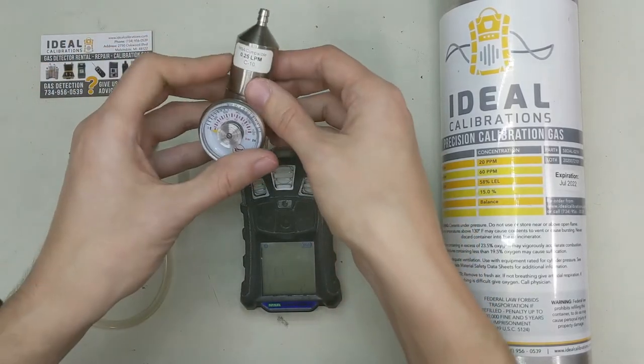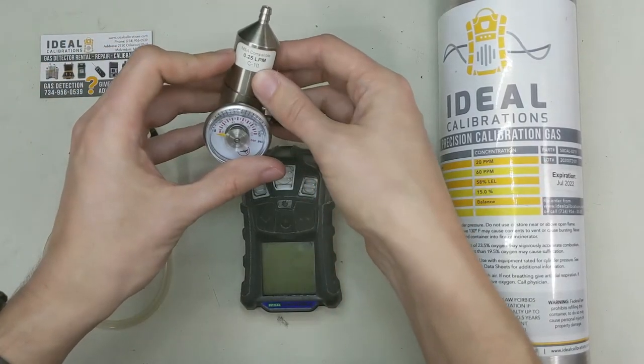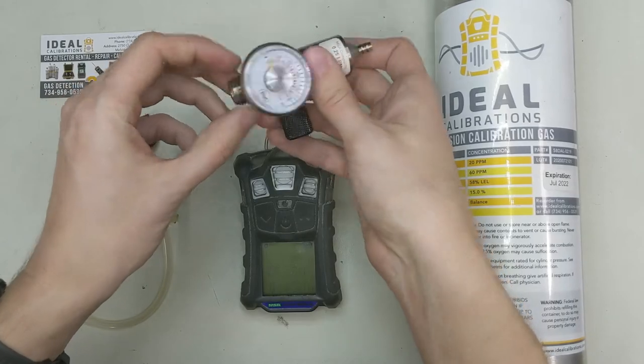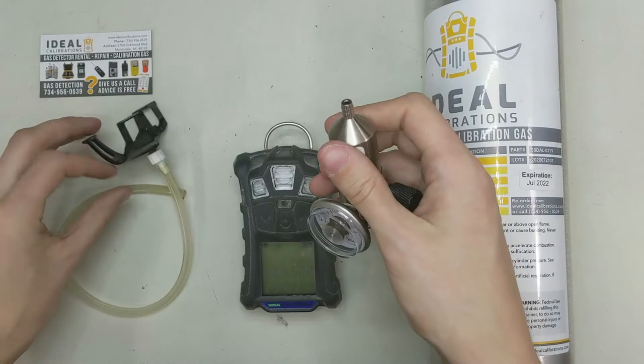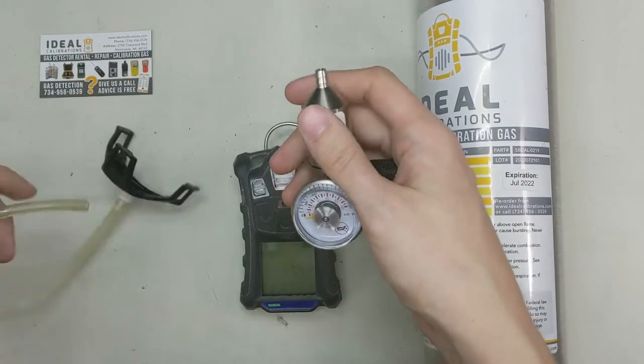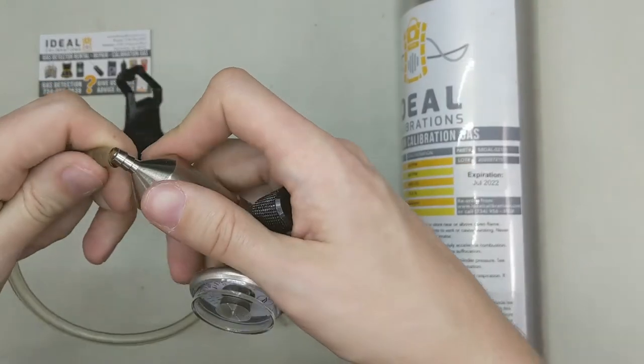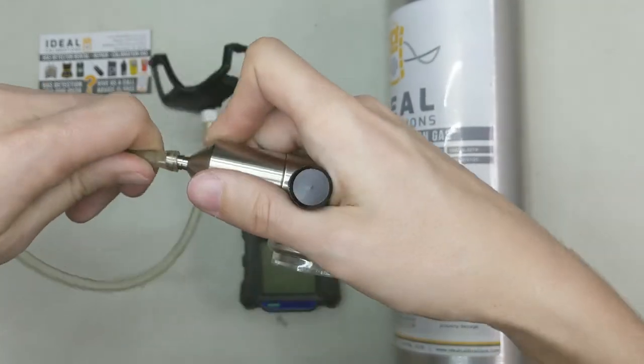In the meantime, we've got a 0.25 liter per minute regulator. It's a C10 fitting like this, and it's a fixed flow on-off. What we're going to do is we're going to take the calibration adapter you got with the monitor. And while this is starting up, going through sensor discovery, we're going to go ahead and attach this here.